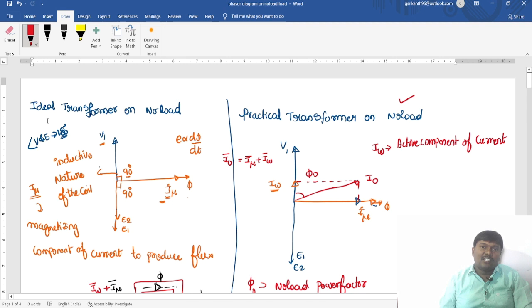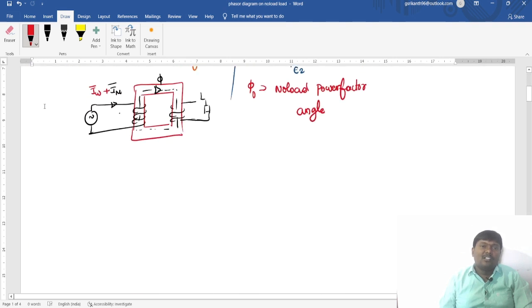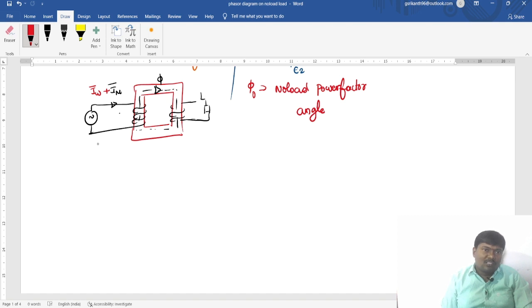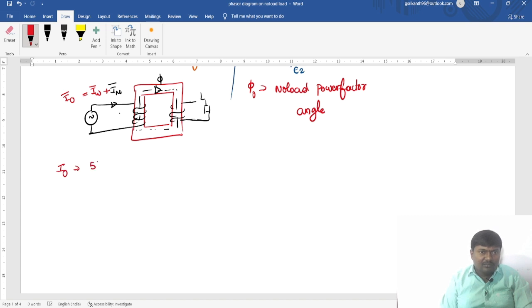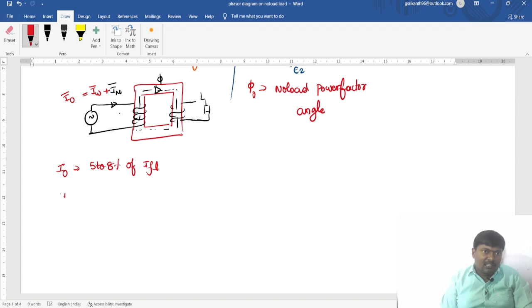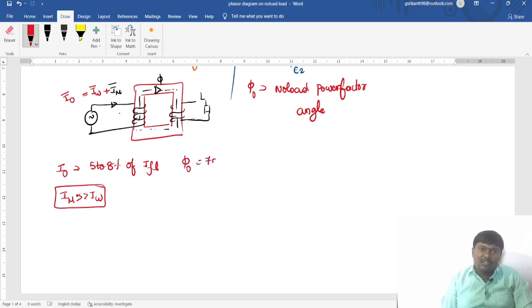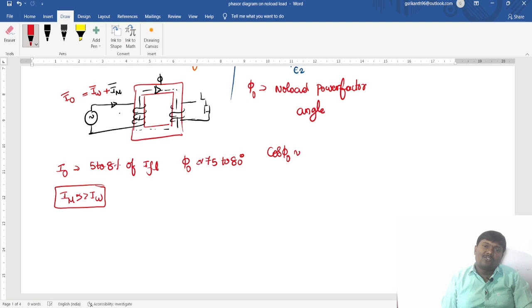This is the phasor diagram of a practical transformer operating under no load condition. The no load current Iw bar is in the range of five to eight percent of full load current. The magnetizing component Imu is much greater than the wattful component Iw. The angle phi-naught is approximately 75 to 80 degrees, and the no load power factor is approximately 0.2 lagging — that is, less than 0.5.